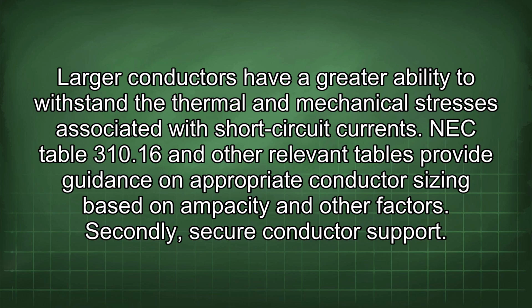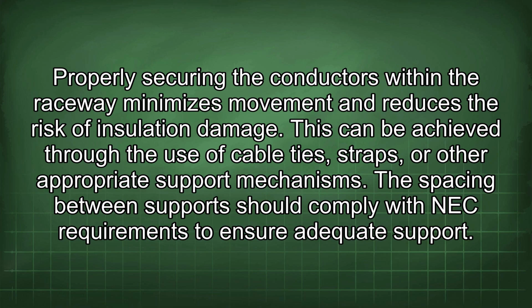Secondly, secure conductor support. Properly securing the conductors within the raceway minimizes movement and reduces the risk of insulation damage. This can be achieved through the use of cable ties, straps, or other appropriate support mechanisms. The spacing between supports should comply with NEC requirements to ensure adequate support.